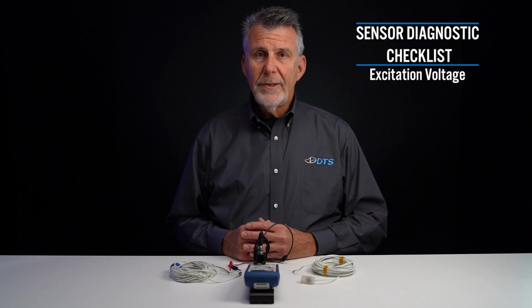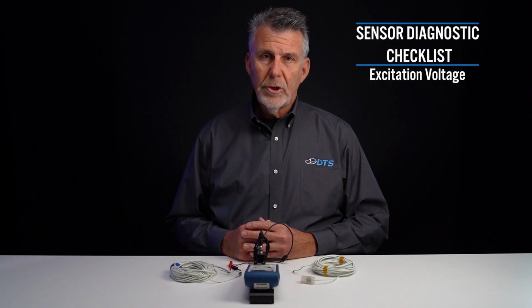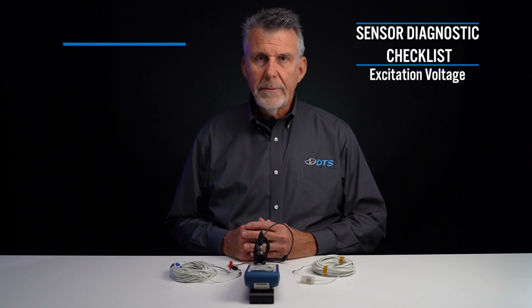First, let's review some of the sensor diagnostic features available in all DTS systems and software. And the goal is, of course, to find sensor problems before you run a test. Some of the things we check when performing sensor diagnostics include excitation voltage checks. This check is designed to find out if you've got a shorted sensor or cable.